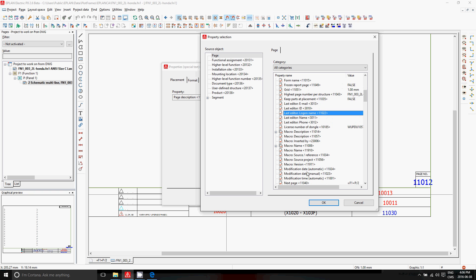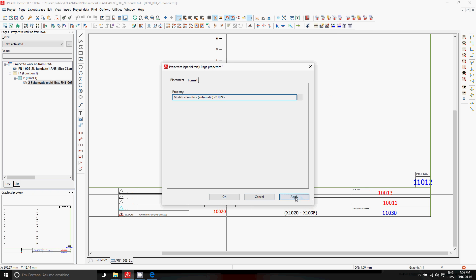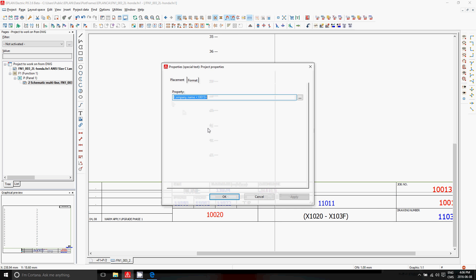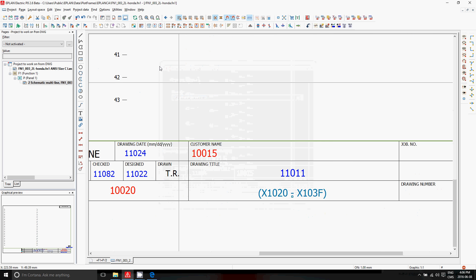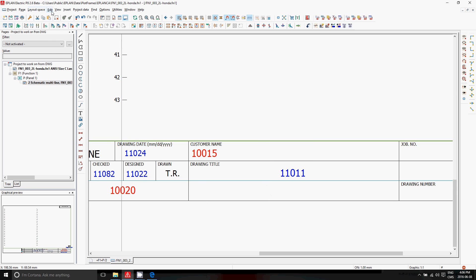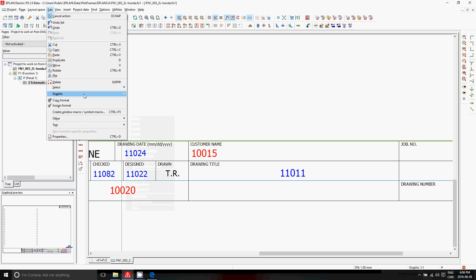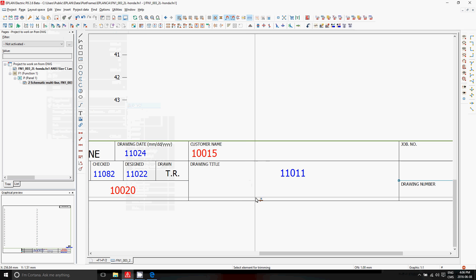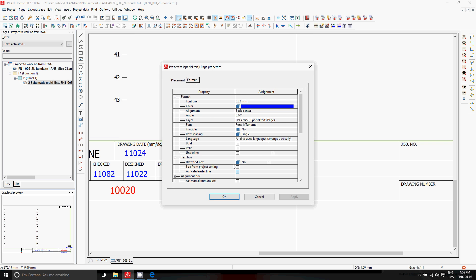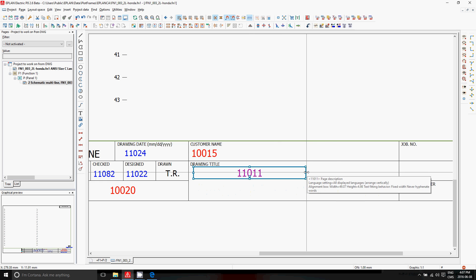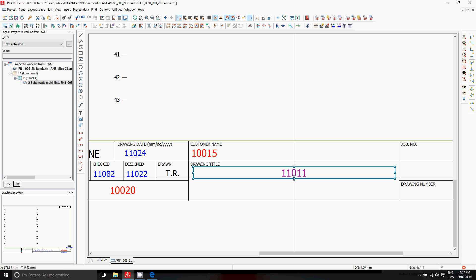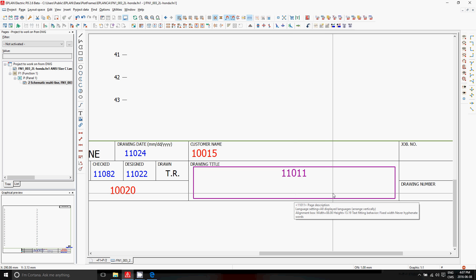Here I'm going to use the modification date — the automatic date — so this means that every time somebody actually modifies the page, it is registered here. Here I will put the project company name, and here I will do the page description. Now in the page description, if you have multiple lines, ePlan has wisely called this a cut-off feature, so I'm just going to trim this off. I will actually format what we call a text box to limit the size of that text, so it should fit right in this box here. Whatever I type in the page description doesn't go over this size.